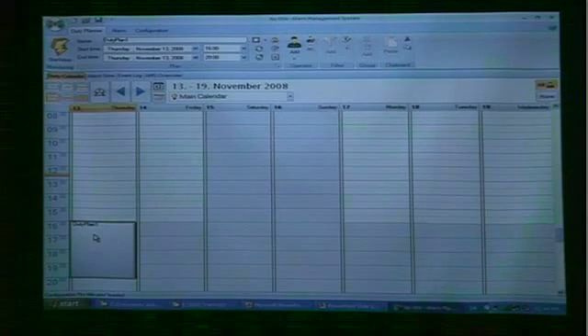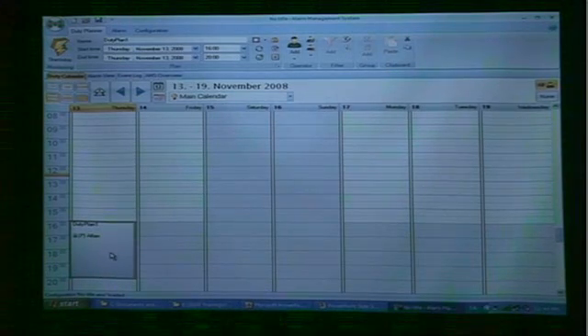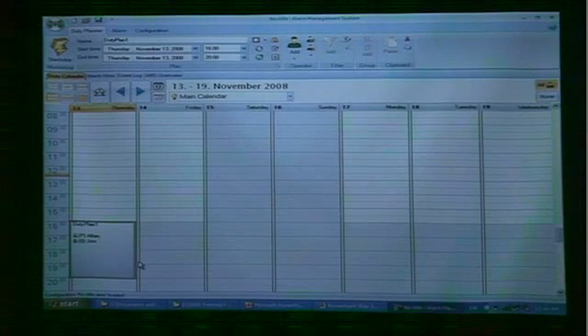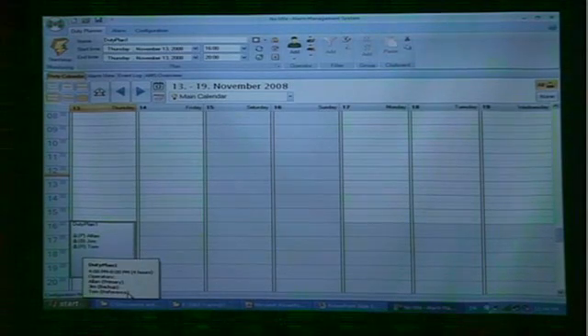I close the dialog box, go over to the duty plan, right click in it, and choose Add Operator. I have three operator types: a primary, a backup, and a reference. I choose Alan as the primary — he will be the operator that receives alarms first from the AMS server. If Alan does not answer, we go over to the backup operator called Jim; he will receive the alarm if Alan does not acknowledge. The third operator type is the referenced operator — this is usually a supervisor who receives all the alarms that come from the AMS system.